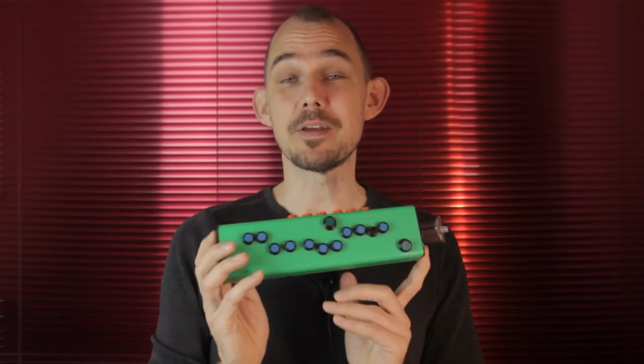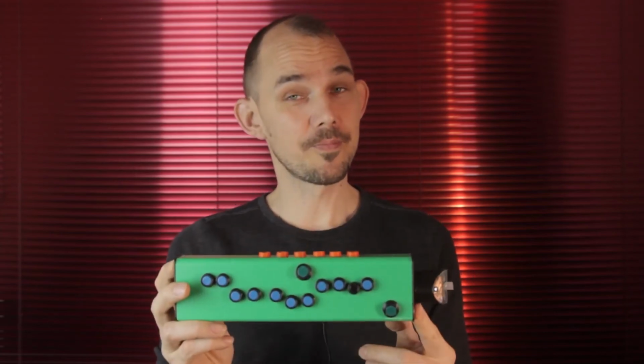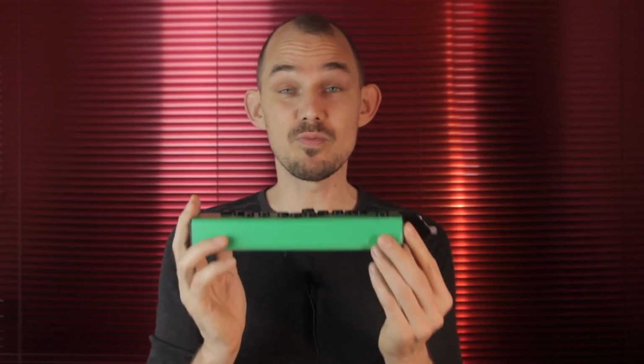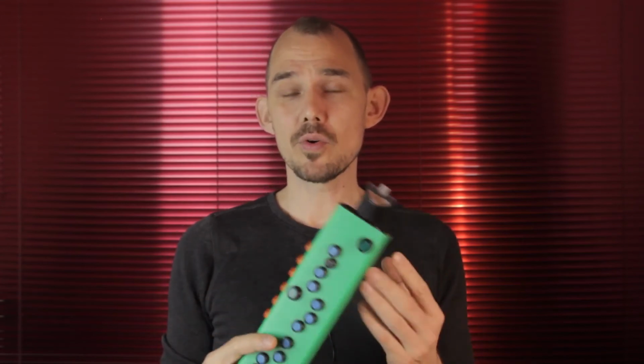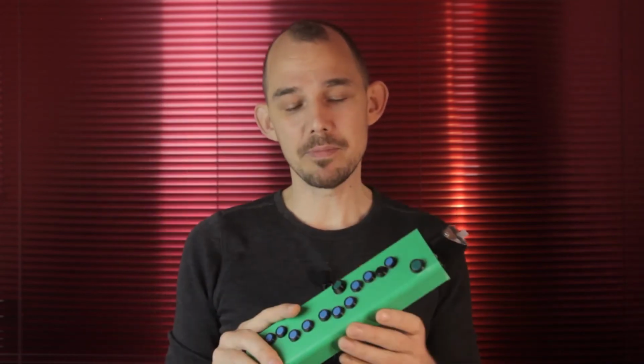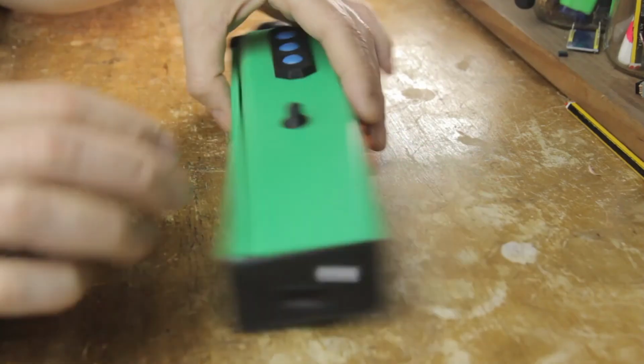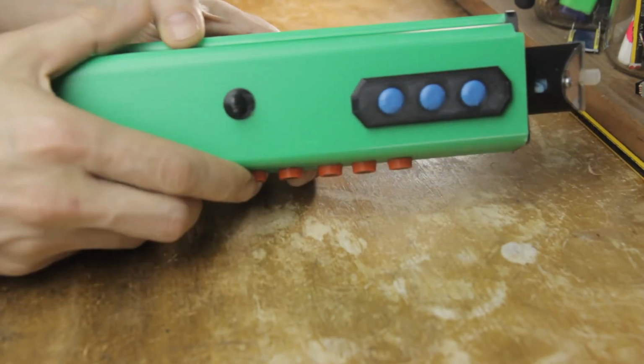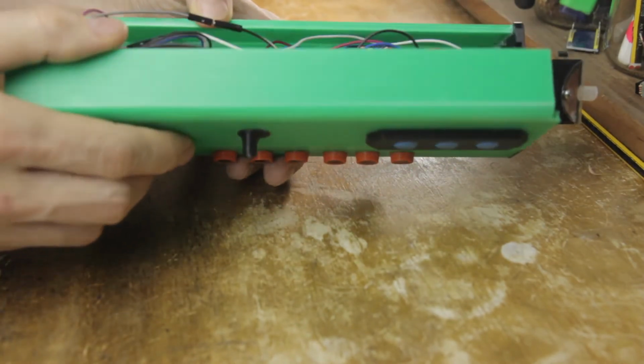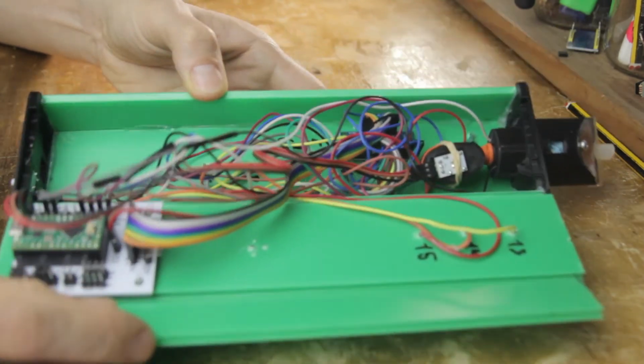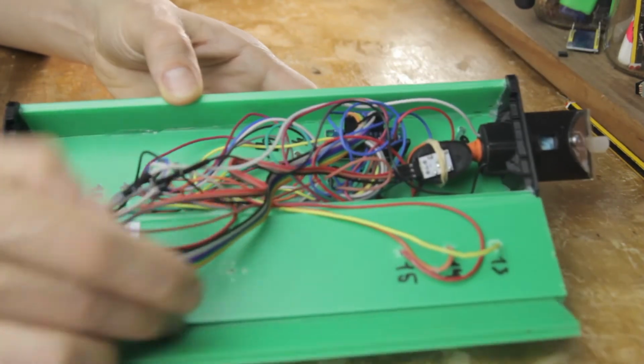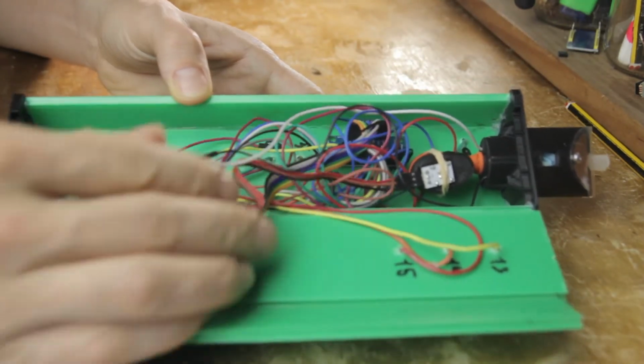Another typical problem with capacitive sensors is crosstalk. If you connect these sensors with really long cables, for example, then those cables essentially become part of the sensors and they can start to inadvertently sense each other. This is most likely to be a problem if you squeeze a lot of cables into a really tight space. The KLIK calibration routine is designed to take some crosstalk and noise into account. And as you can see here, there is quite a lot of leeway. Even the mess inside this one works quite well.